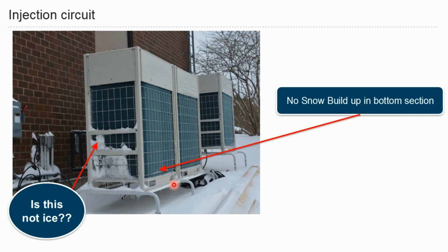This is an example from a project in Boston. As you can see, there's no ice accumulation happening at the bottom of the heat exchanger circuit. Over here, you see some sort of ice formation happening, but just keep in mind that this is only on the coil guard side. And if you put your hand around the coil guard and the heat exchanger, the left side you see over here, you wouldn't be seeing any ice or snow accumulation there.